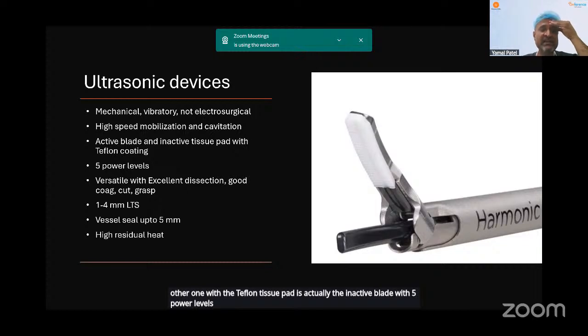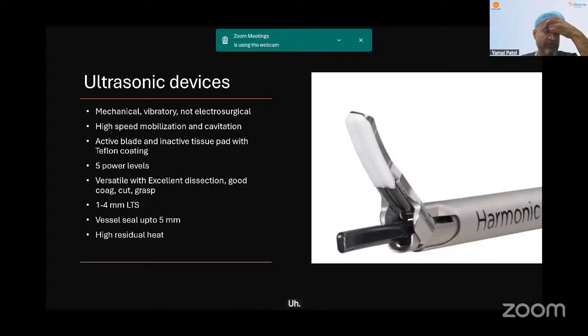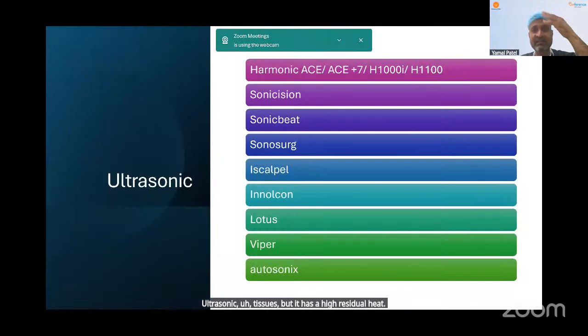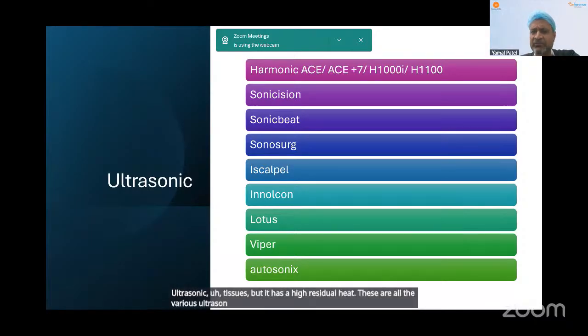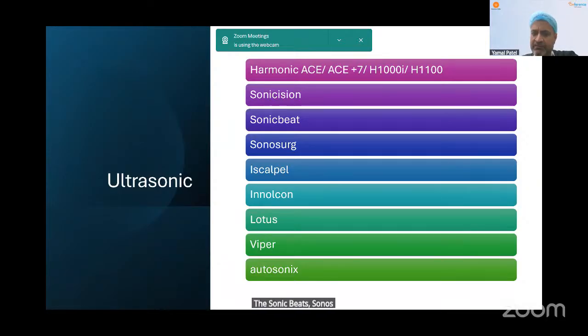It is versatile with an excellent dissection, good coagulation, cut and grasp method. It gives you a 1 to 4 millimeters lateral thermal spread and seals easily up to 7 millimeters in the newer ultrasonic tissues, but it has a high residual heat. These are all the various ultrasonic types of instruments we have: Sonicision, Harmonic, the Sonic Beat, Sonosurg, iScalpel, Innolcon, etc.